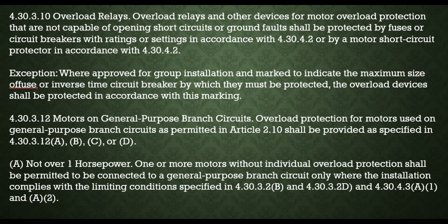Overload relays incapable of opening short circuits or ground faults must be protected by fuses or circuit breakers per 4.30.4.2 or a motor short circuit protector per 4.30.4.2. If approved for group installation and marked with a maximum fuse or breaker size, protection must follow that marking.